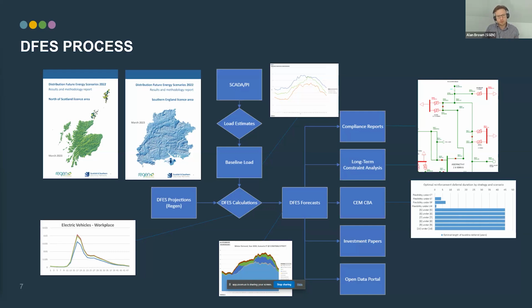What we look at as a baseline is the existing demand on our network. We pull together data, perhaps from the previous financial year, and look at what the monitoring is saying at our substations. We use SCADA systems, a series of VTs and CTs on the network, to calculate what the demand looks like. We offset generation downstream of those monitors so we get a true representation of gross demand at that substation or asset we're forecasting.